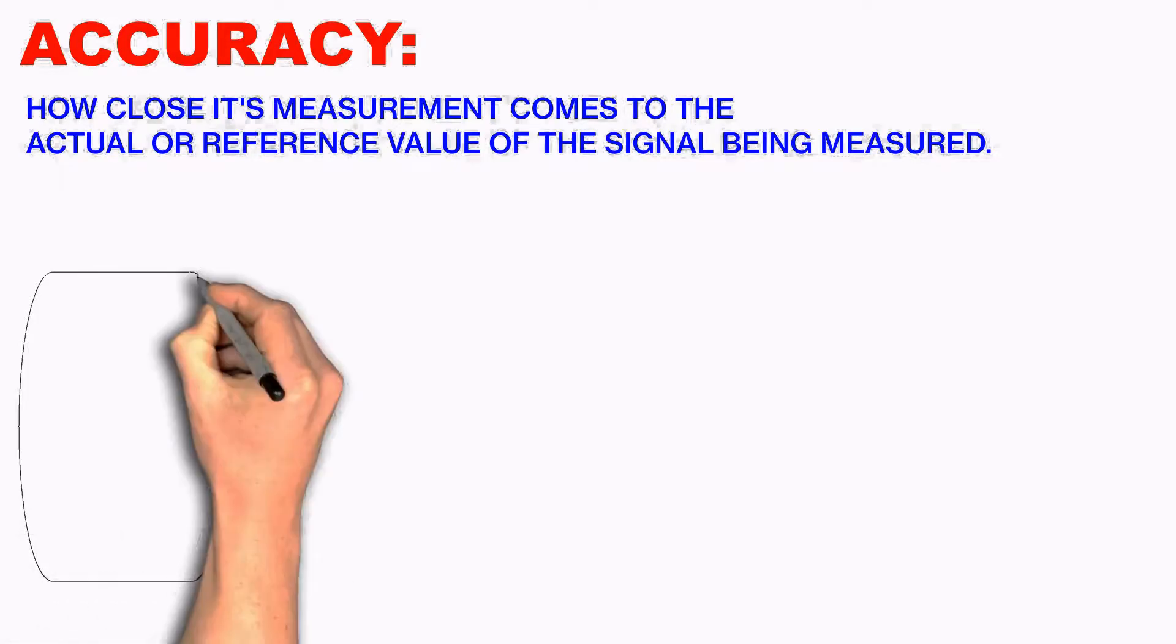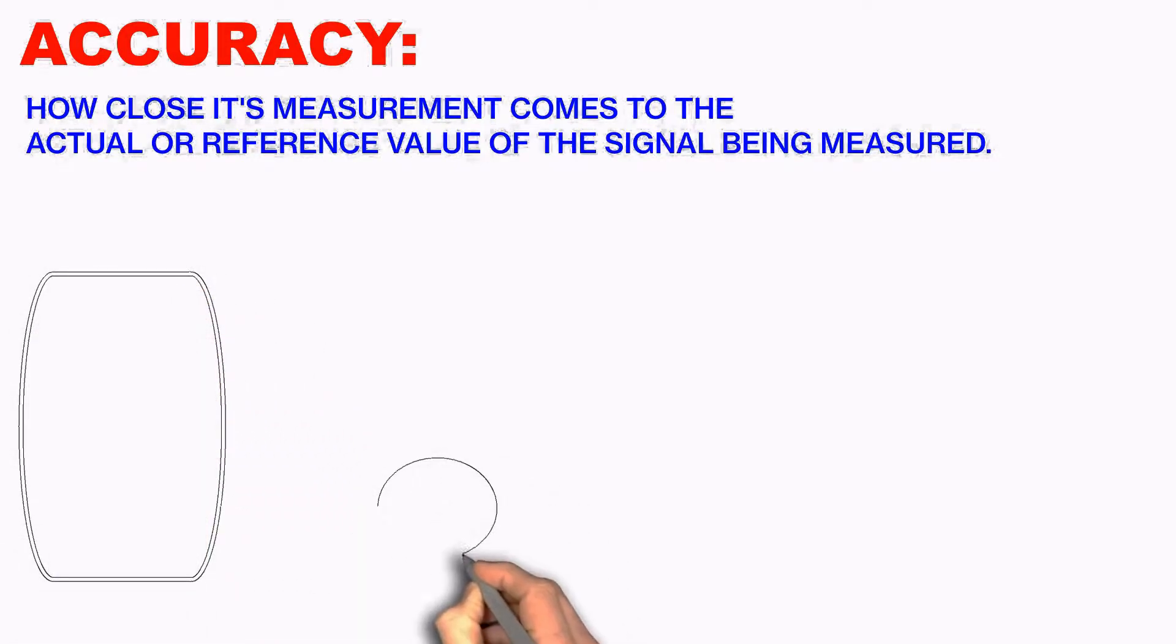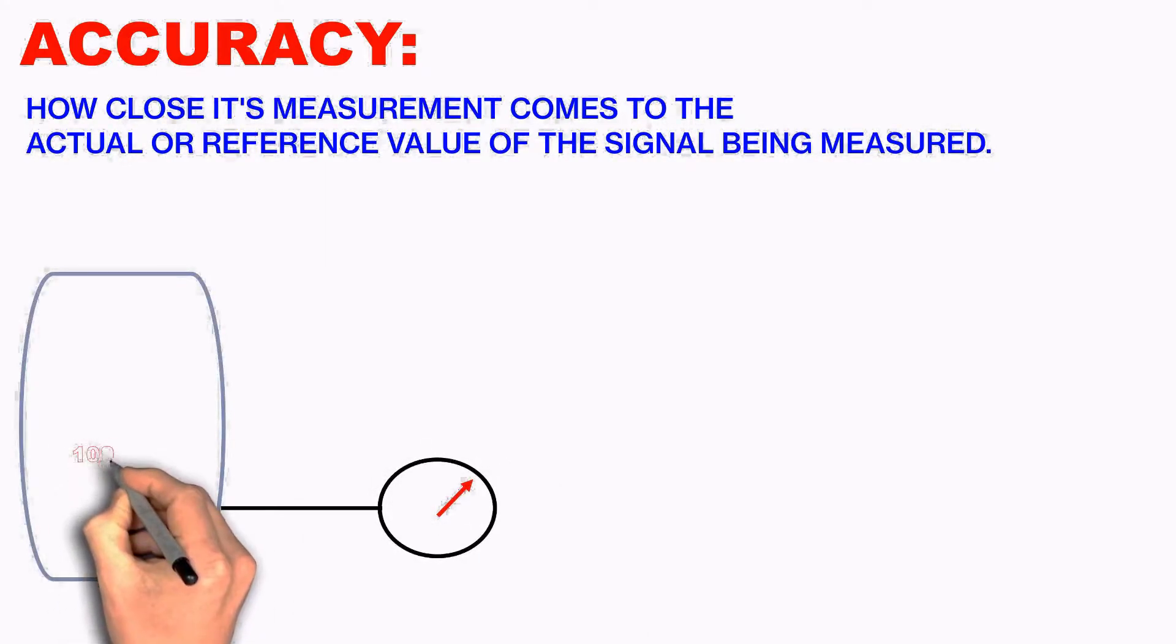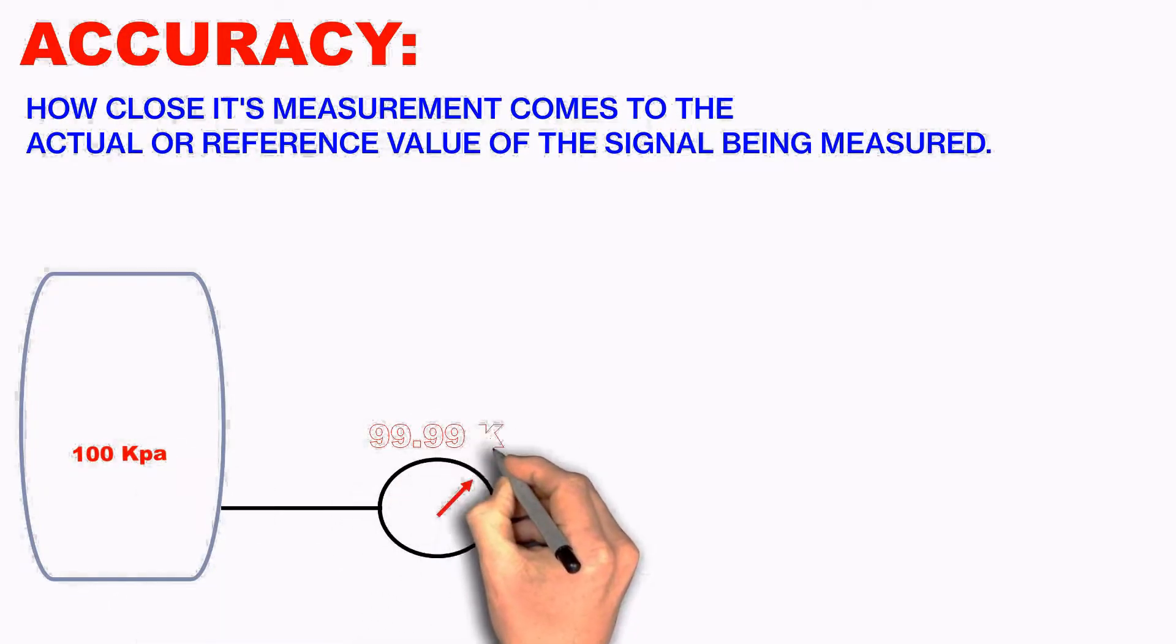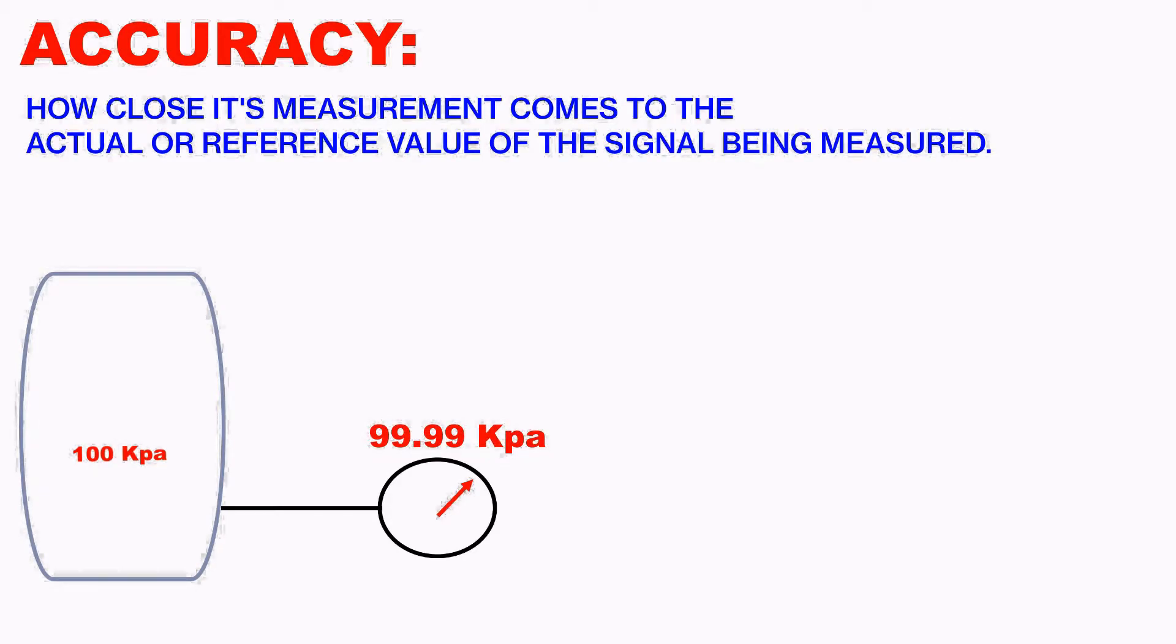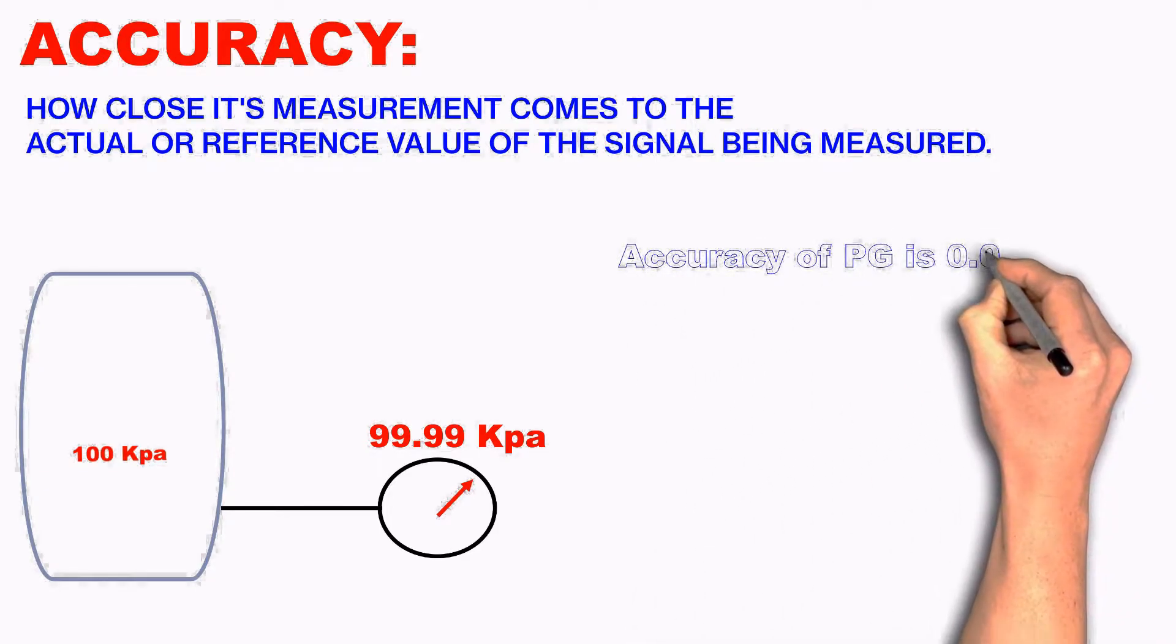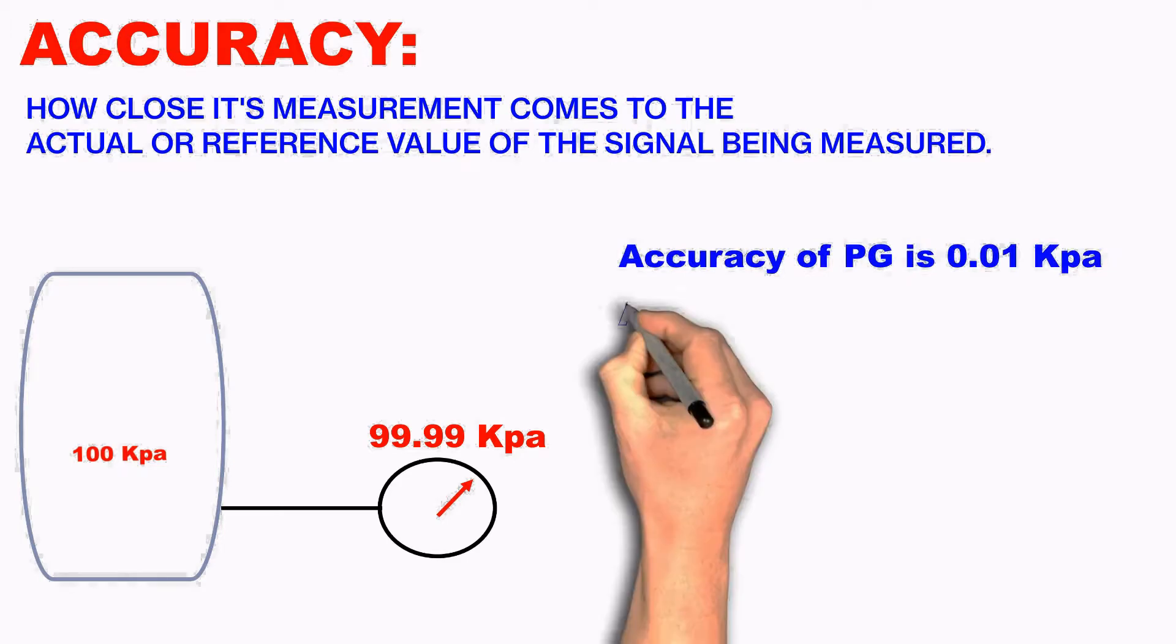In our case, let's see a vessel in which actual pressure is 100 kPa, and I have a pressure gauge or a pressure transmitter. And now it's measuring the pressure as 99.99 kPa. So the actual pressure of the vessel is 100 kPa, whereas the pressure equipments like pressure gauge or pressure transmitter reads 99.99 kPa. So the error here is 0.01, and that's the accuracy.